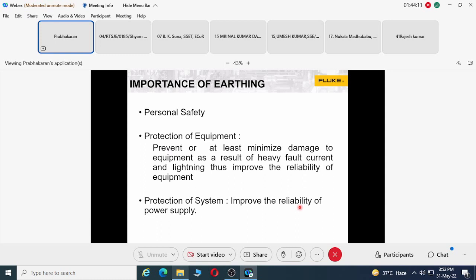For protection of equipment, every electrically operated device needs protective earthing. If that protective earthing is not proper or not connected, something going wrong inside the device can give a leak on its body, or it can kill the device itself. And if there's a leakage on the device, someone touching it may also get a shock.